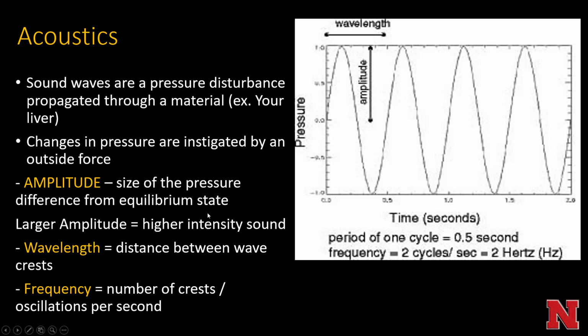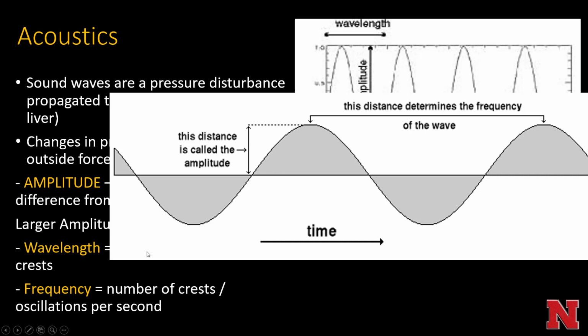There's wavelength and frequency, which are probably the two most commonly discussed things in terms of sonographic physics. Wavelength is just the distance between wave crests. Frequency is the number of crests or oscillations per second. So it's pretty intuitive: if you have a wave with more crests per second, it's going to have a shorter wavelength. This distance is called the amplitude, again, from the baseline to the maximum pressure disturbance. This distance is the wavelength, which determines the frequency.